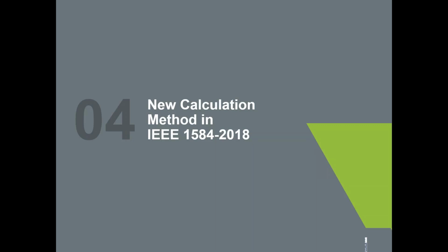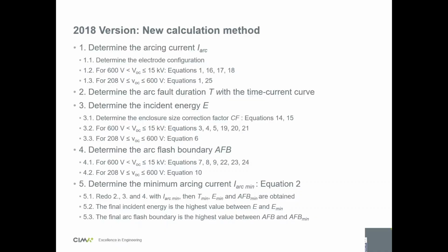So the new equations now. The new method is still about the same method. You find your arcing current. To find your arcing current, you need to specify your electrode configuration. Then you calculate your arcing current. Then you find your fault duration with the time current curve. For example, EasyPower does this automatically for you. Then you calculate the incident energy using a bunch of equations. Then you calculate your arc flash boundary with some other equations.